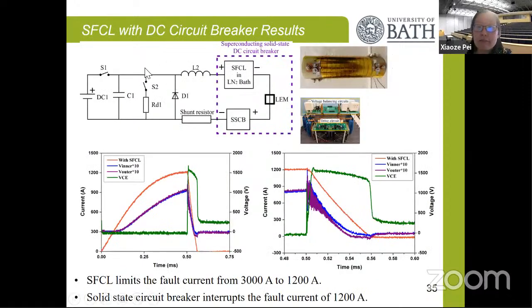So the next step, we integrate the superconducting fault current limiter with the DC circuit breaker. We use the fault current limiter to limit the fault current levels. The prospective fault current level is 3,000 amps, and you can see it's limited down to 1,200 amps. And then the solid state DC circuit breaker is able to interrupt the fault. So we are able to demonstrate effective fault current limitation and then very quick current interruption.